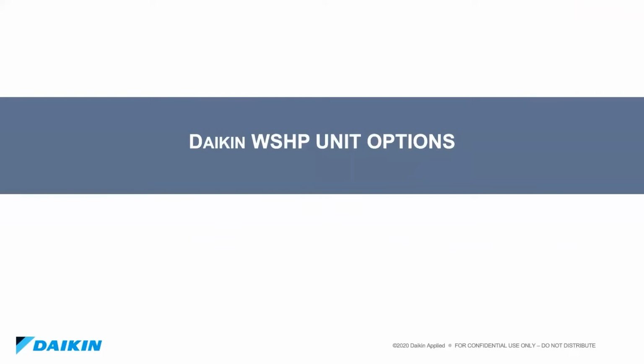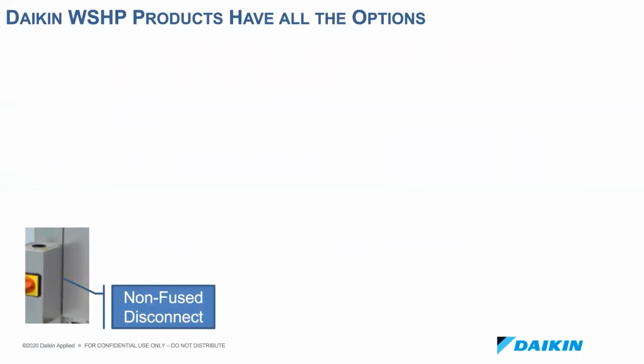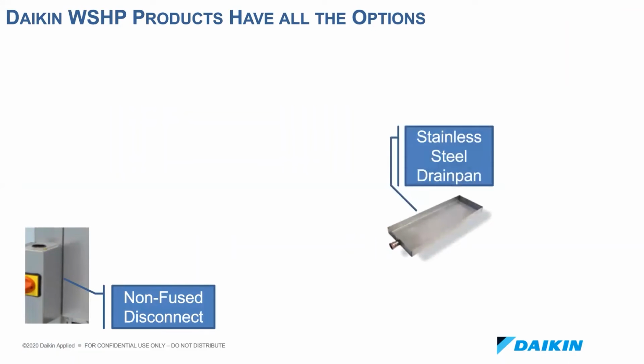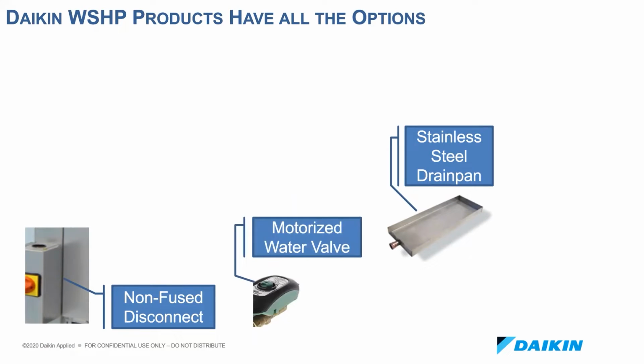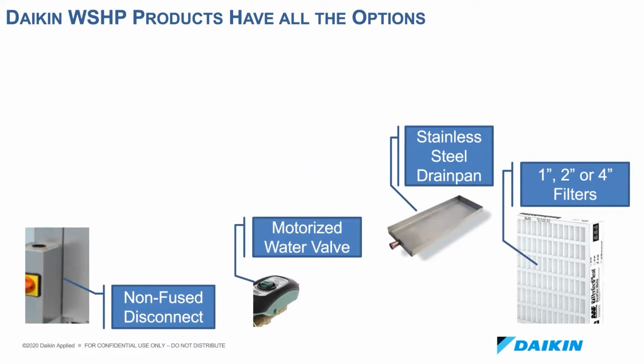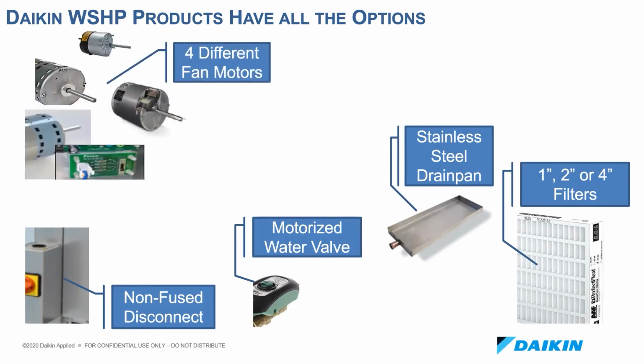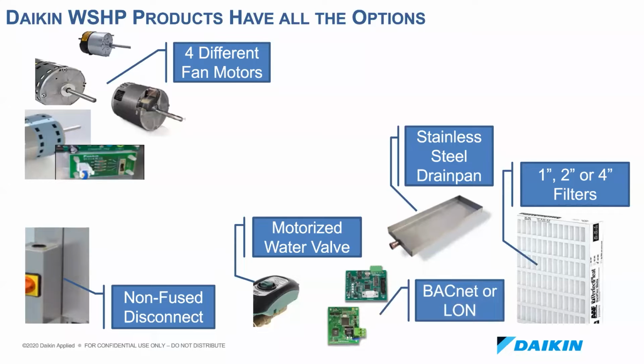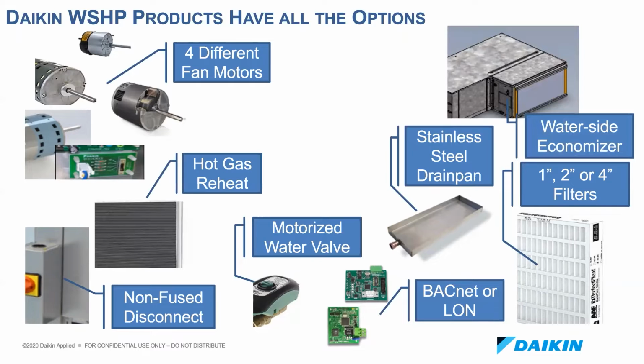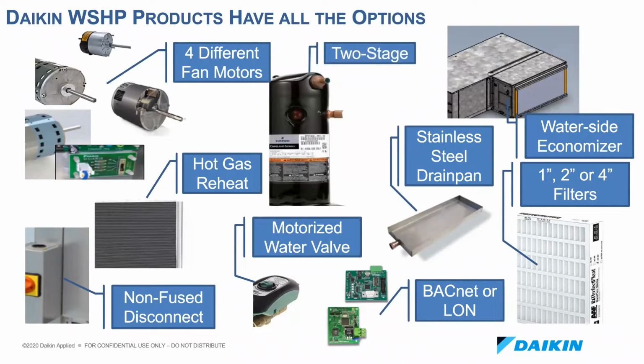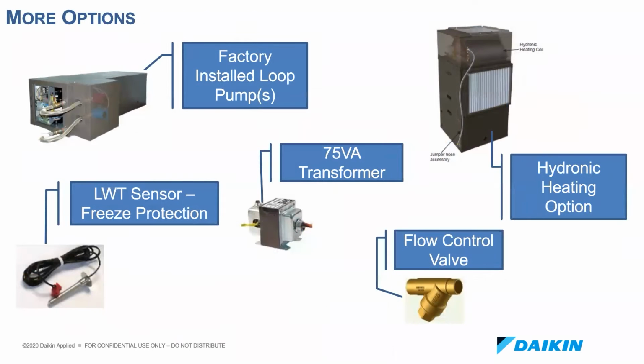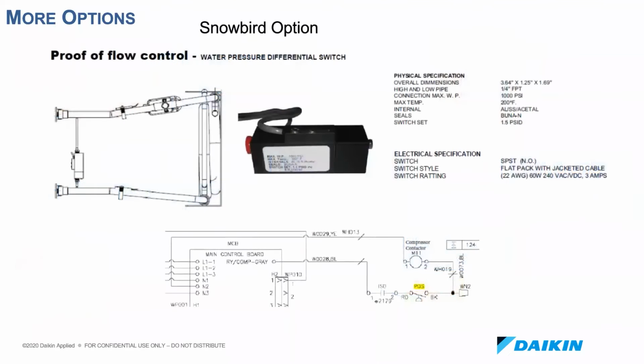Next is our water source heat pump unit options and accessories. Starting with a non-fused disconnect switch, a stainless steel drain pan, a motorized water valve for variable pumping applications, different air filters, 1 inch, 2 inch, or 4 inch, 4 different fan motor types, a BACnet or LonWorks communication card, a water side economizer option, hot gas reheat option, and a 2-stage unloading scroll compressor for the 2-stage models. We also offer factory installed loop pumps, a hydronic heating option, leaving water temperature sensor for freeze protection, a 75 VA transformer, and an auto flow control valve. We also have a water pressure differential switch for proof of flow control.